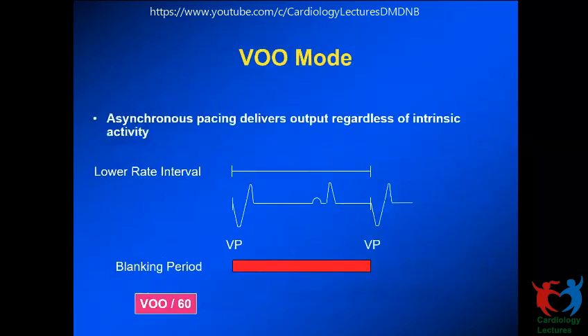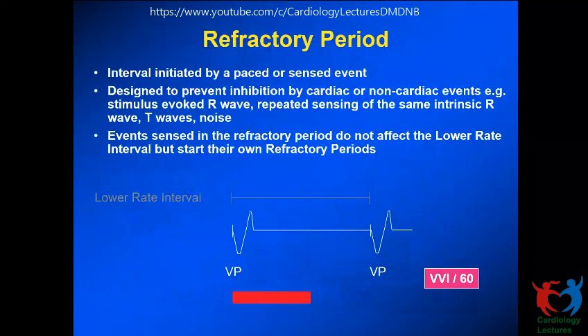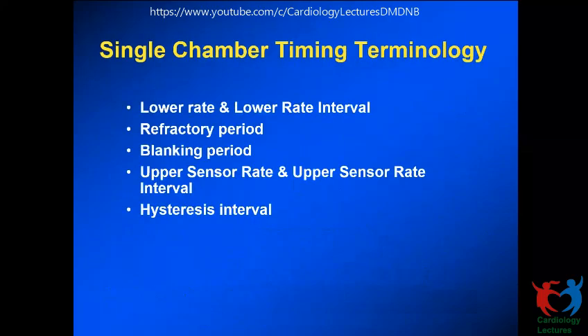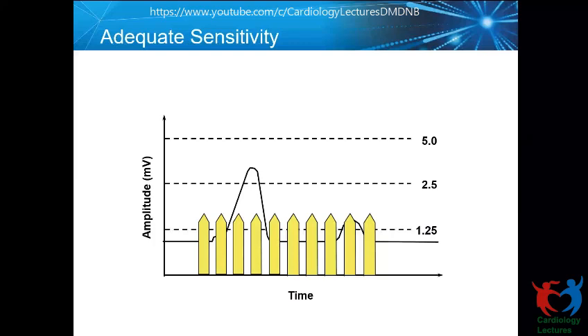So just to go back to my sensing picture. Yeah. In this one, we have set a sensitivity; this is my amplitude scale. Let's say I've set a sensitivity of 1.5 millivolts. The fence represents my sensitivity setting. And this one is the R wave. This R wave is about 3 millivolts. So the R wave amplitude is bigger than the sensitivity setting. And every time the amplitude of the intrinsic R wave or any electrical event is taller than the sensitivity setting we've made, the device will sense it. Right? So this, let's say, is an optimal sensitivity.